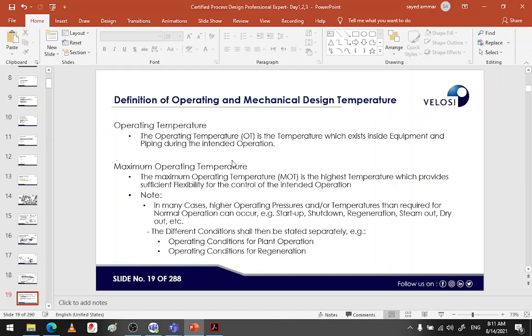Because normally if you are using mild steel or carbon steel, the lowest temperature you can see is minus 29. Below minus 29 Celsius, the material will have some brittleness, and if you just hit it with any hammer, it will break like glass. So we have to make sure that this metal does not go below minus 29. This happened to me personally during a startup. I was in the Emirates starting up a platform.